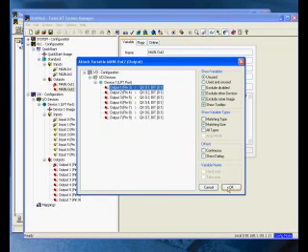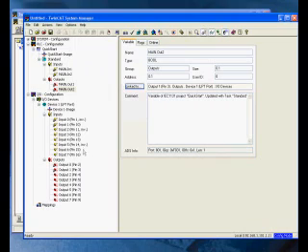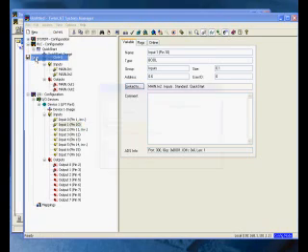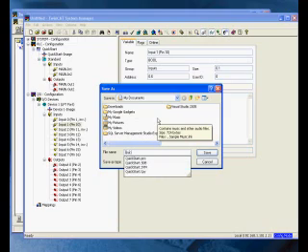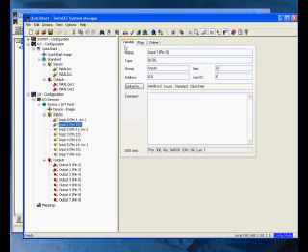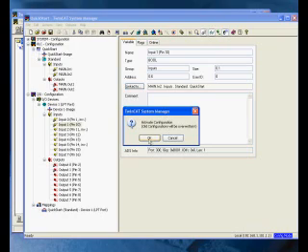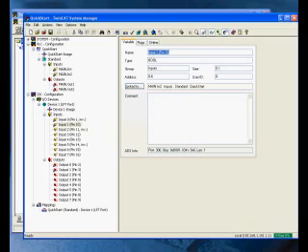and once that's done, you can kind of quickly see I've got little shortcut arrows showing that they're linked. Now let's save the project, which is the system manager file. I'll give mine the name, save it in my documents also. So now we've linked that to hardware, so we're going to generate mappings. We're going to check it, verify everything, and then I'm going to activate my configuration. So now I'm basically saying the addresses I defined in my PLC program are going to be linked to physical I/O, and that's what the mapping is for.